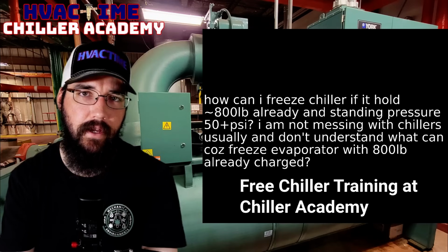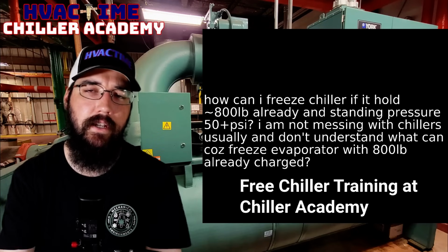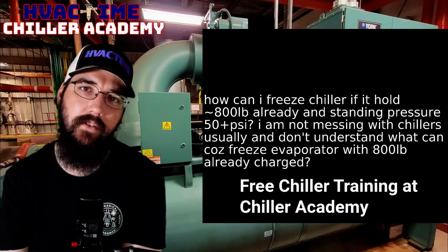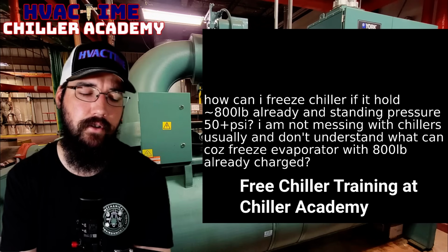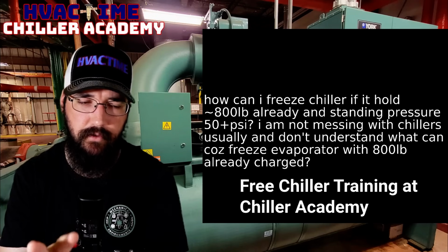If you're above that, the volume of refrigerant does not matter. Okay? You can get into systems where 800 pounds is just a portion of it. Now, in our context, that's probably the majority of your charge, I would assume, if not your entire charge. And that's the key takeaway here: saturation, saturation, saturation. I'm just driving that home.